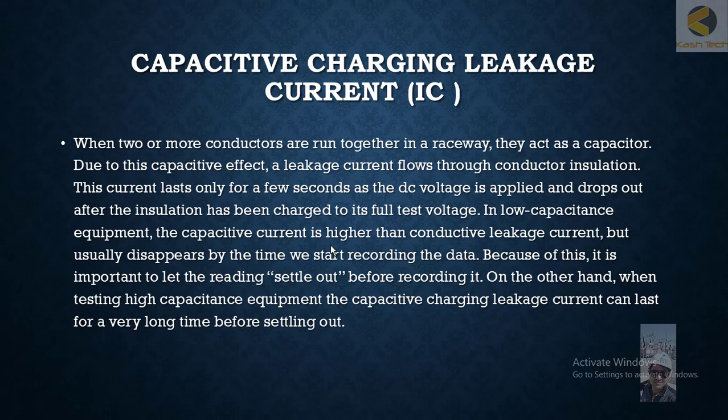The topic is capacitive charging leakage current. When two or more conductors are run through a raceway, they act as a capacitor. Due to this capacitive effect, a leakage current flows through the conductor insulation. This current lasts only for a few seconds as the DC voltage is applied, and drops out after the insulation has been charged to its full test voltage.